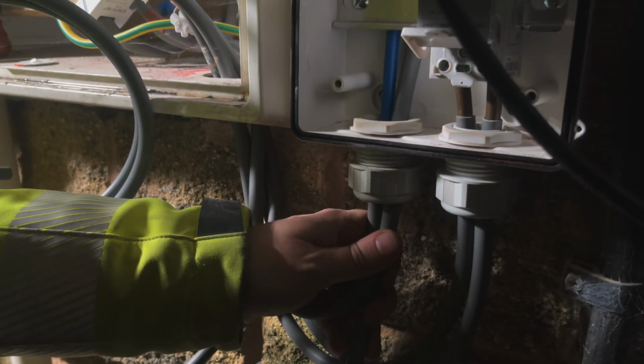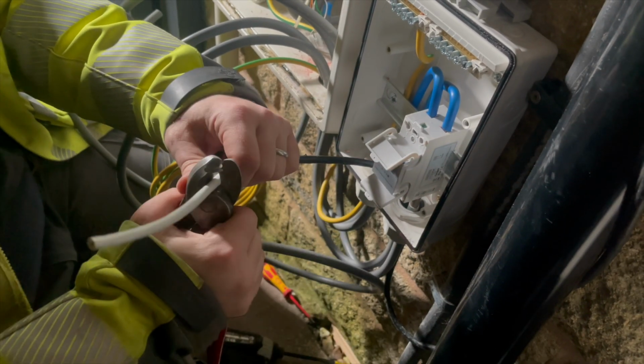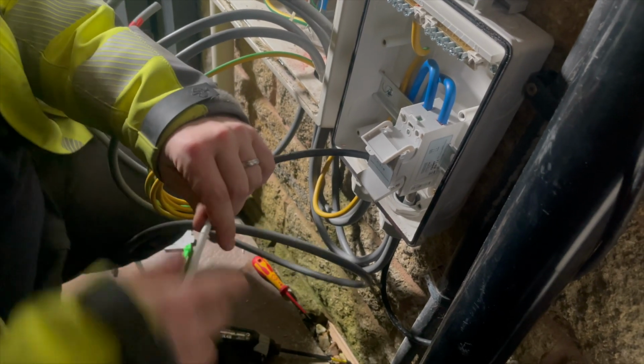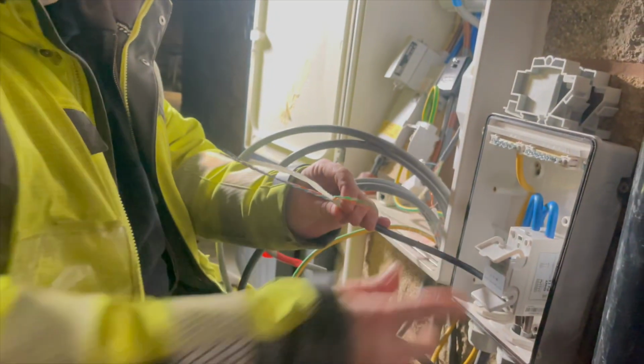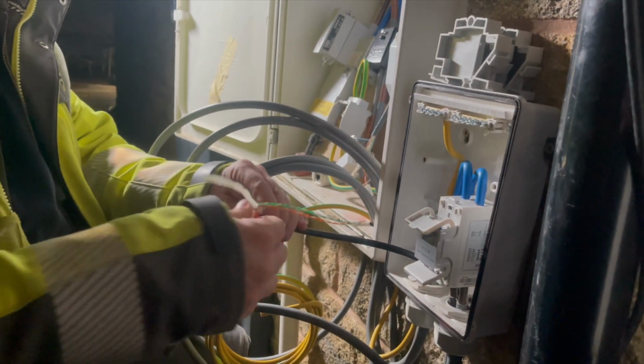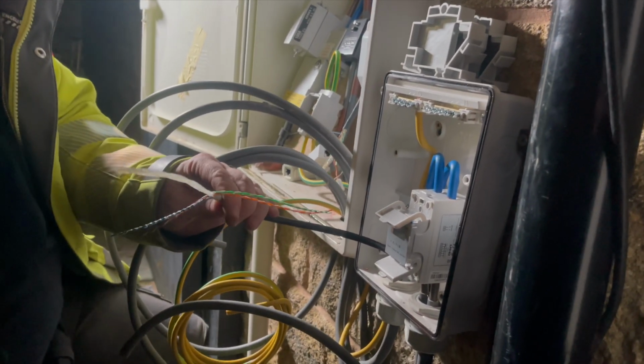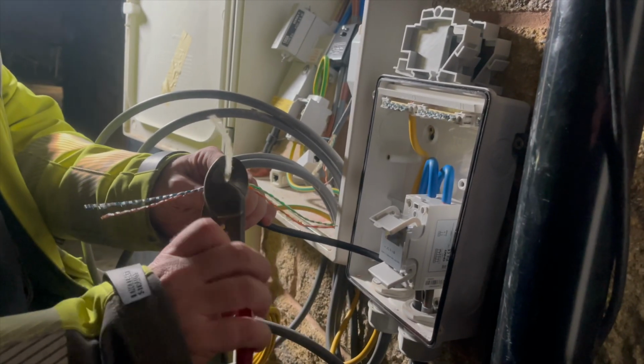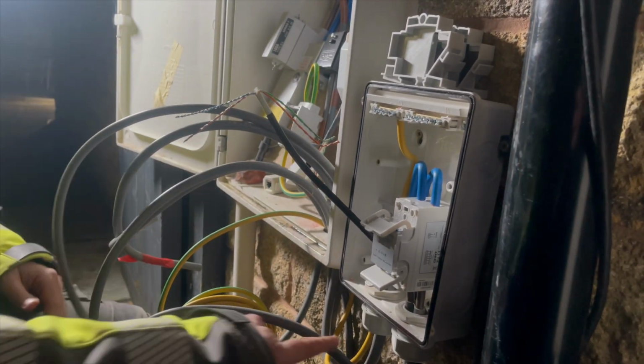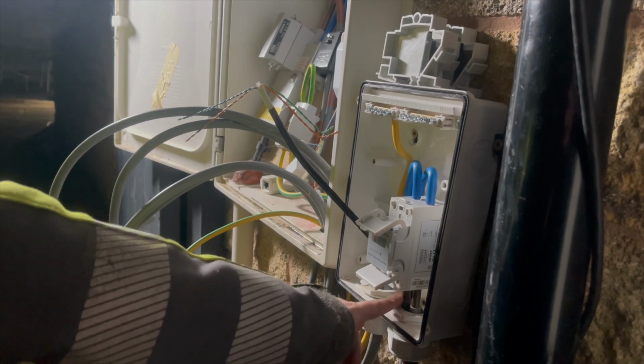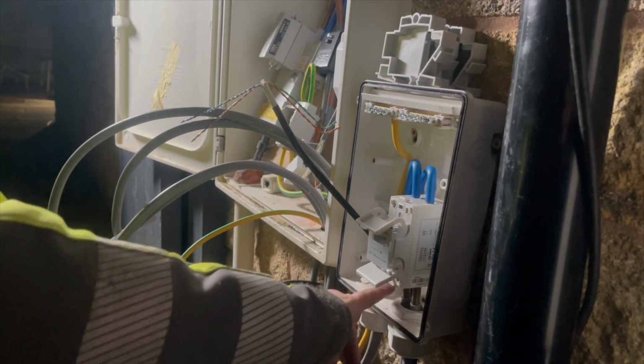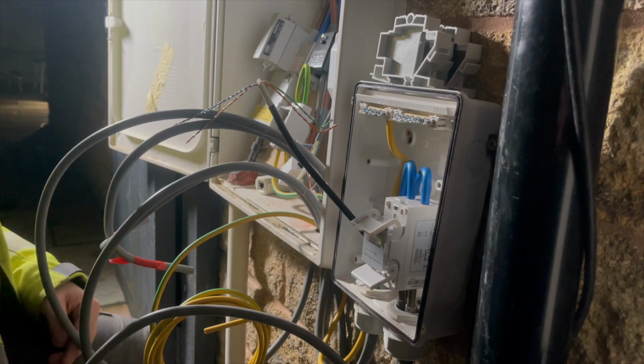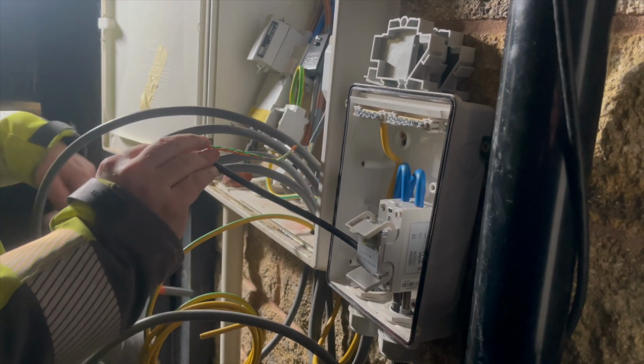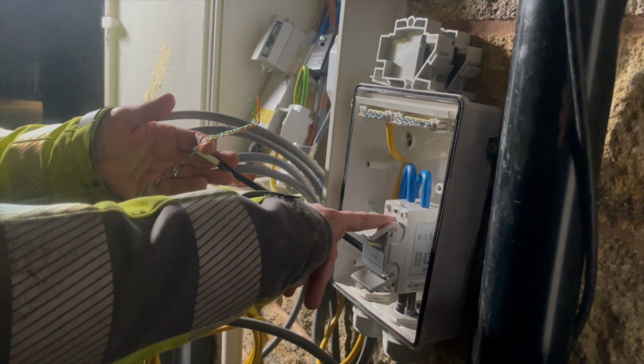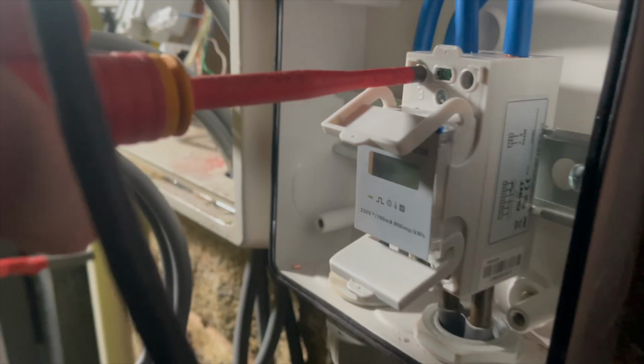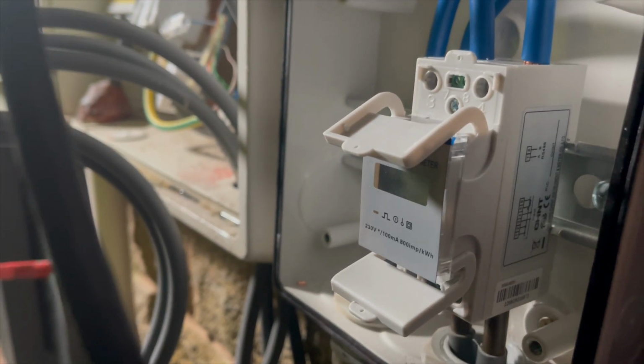Just very quickly, Lee, what you've got in there now, you're basically putting in this Cat 5, and it's going to essentially a mini smart meter slash CT clamp. That's right, yeah, so it functions as a CT clamp and a meter. It measures the current, I assume coming through either the live and neutral side or both, and then transmits this data via these little terminals here through this Cat 5.